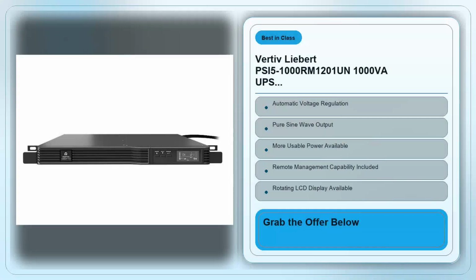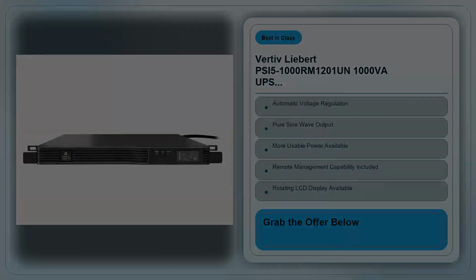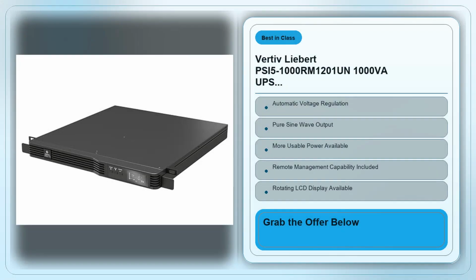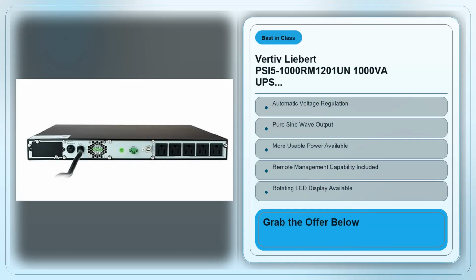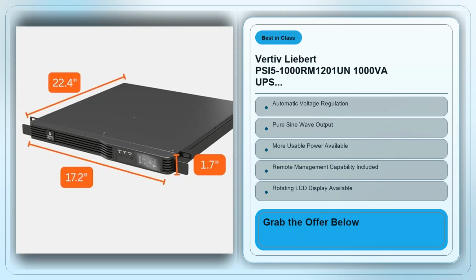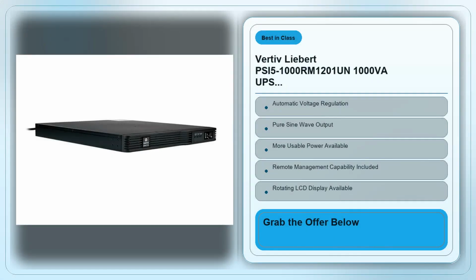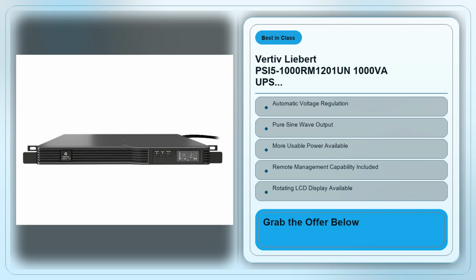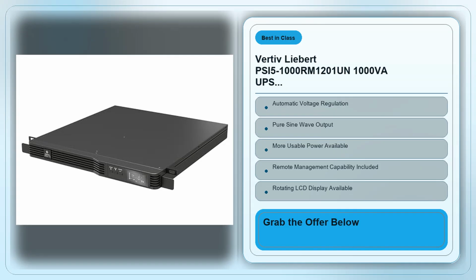First off, who should even consider a 1U UPS? If you're running a compact rack, say, a 2U or 4U chassis that's already squeezed into a closet or a small office and you need to keep a handful of critical devices online for the occasional outage, this is the kind of size that fits without forcing you to rearrange. It also makes sense for power-hungry workstations that demand a clean sine wave, like video editors or engineers running high-end graphics cards. On the other hand, if you're looking to protect a whole data center, a single 1000VA unit will feel like a band-aid.